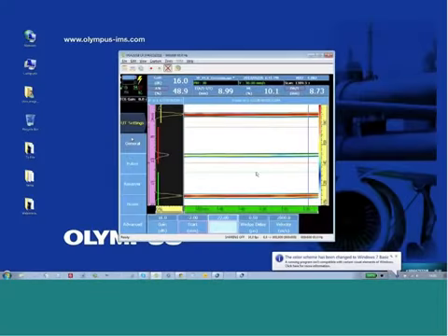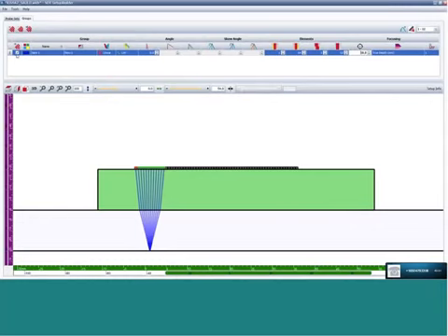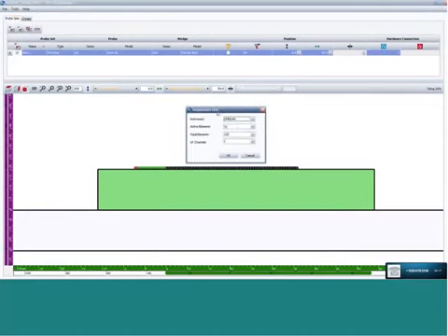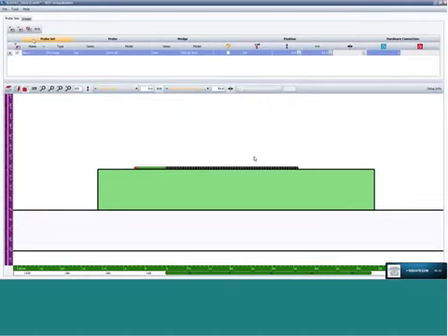So I'm going to step away from the presentation for a moment, and we're going to look at this same setup in an application or a program called the NDT Setup Builder. The Setup Builder software is designed to be a calculator with ray tracing capabilities for simple geometries. The instrument or acquisition unit is entered to tell the focal law calculator the limits of our active pulsers and total elements in the probe and UT channels. Once this is entered, the software isn't going to allow me to create a condition that's not compatible with the instrument I'm using.